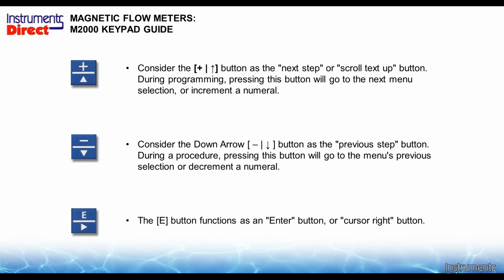And program your meter, let's just face it, this is a mag meter. And 9 out of 10 times out of the box, plumb it in line, power it up, and go home. And so that's most of the cases you're going to use a magnetic flow meter there. Should you need to trim something, in that case there's 3 buttons on the front of the display. Here's the picture of the 3 buttons there.